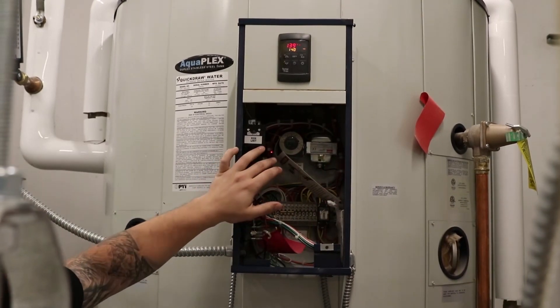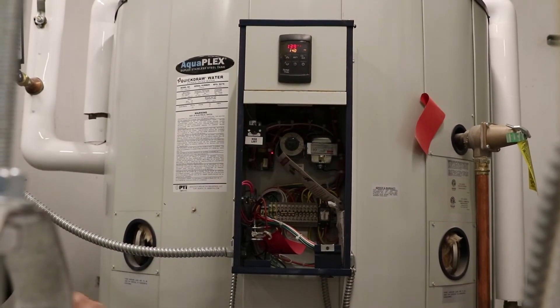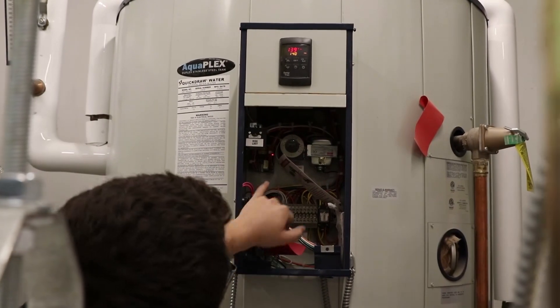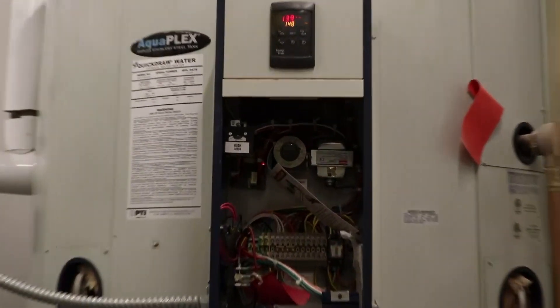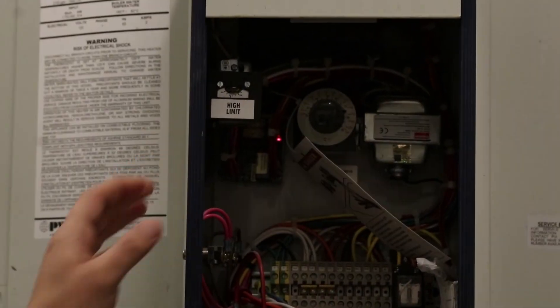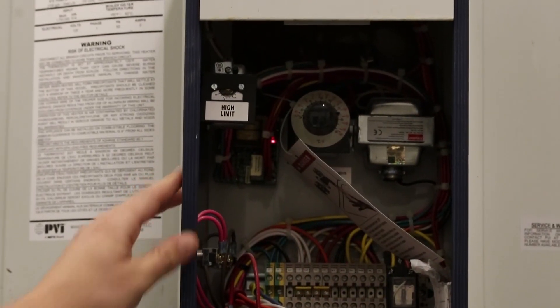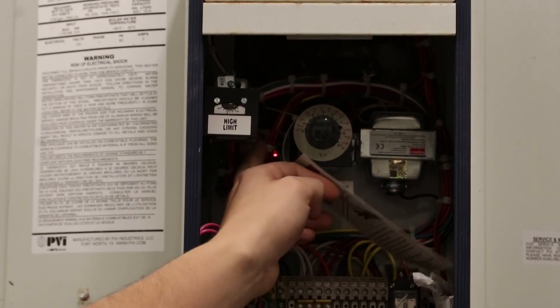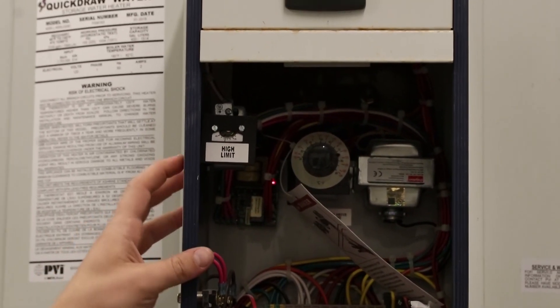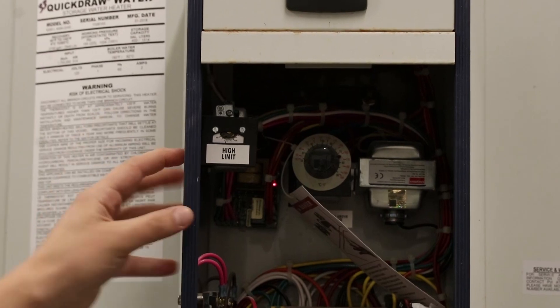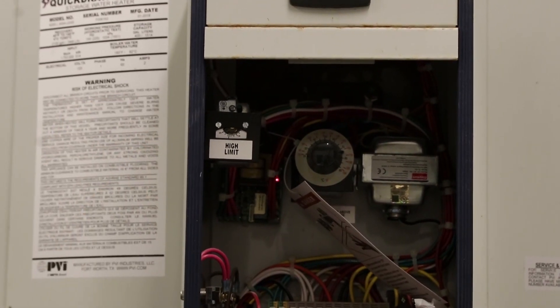The other safety, in addition to the manual reset high limit, is the low water cutoff control. You'll see that green circuit board that's in the control panel just behind the high limit. Hopefully on the camera, you can see there's a red LED light on on that board. That red LED light being present tells me that this control is sensing water and is satisfied and is not preventing operation of the water heater.